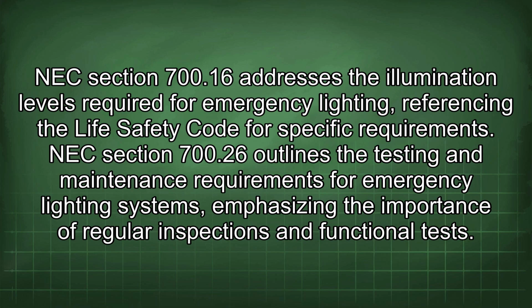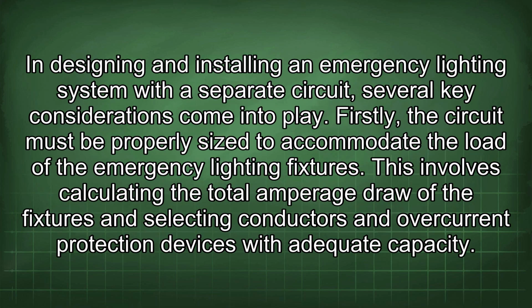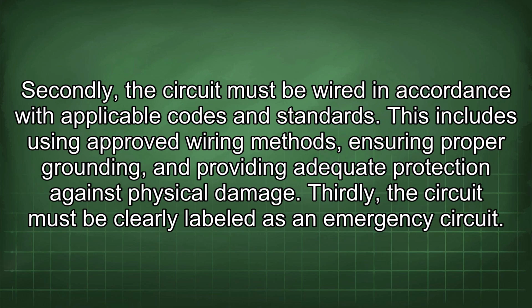In designing and installing an emergency lighting system with a separate circuit, several key considerations come into play. Firstly, the circuit must be properly sized to accommodate the load of the emergency lighting fixtures. This involves calculating the total amperage draw of the fixtures and selecting conductors and overcurrent protection devices with adequate capacity. Secondly, the circuit must be wired in accordance with applicable codes and standards. This includes using approved wiring methods, ensuring proper grounding, and providing adequate protection against physical damage.